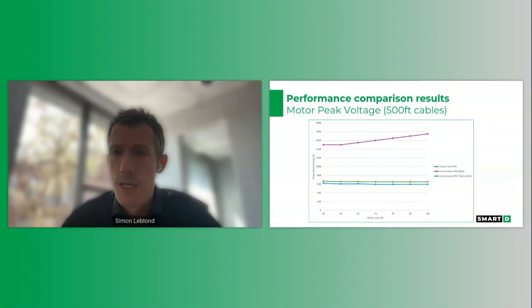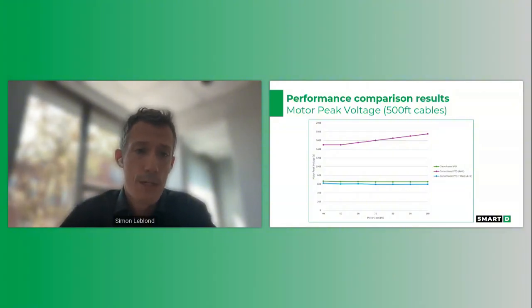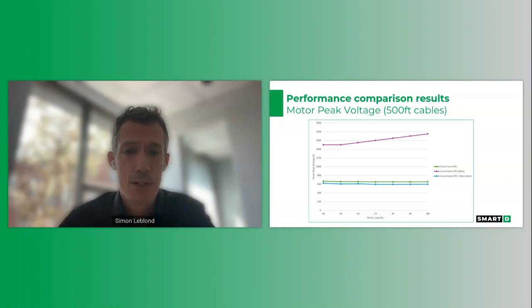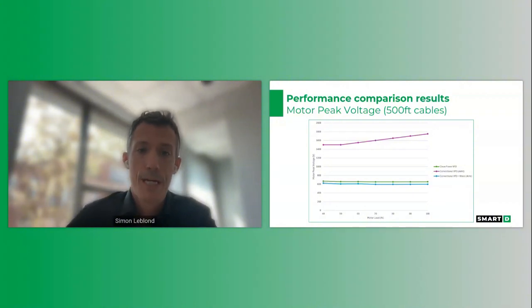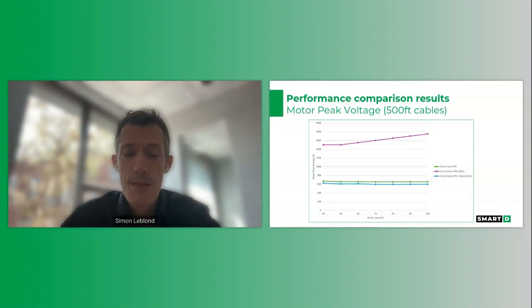Now, continuing, common mode is one of the villains you talked about, Bobby, but the other one is the motor peak voltage, which is made worse as we get longer and longer cables. In this case, with 500 feet of cable, you can see that the conventional VFD is definitely above the 1,000-volt limit that we find in many cables. Actually, we can even ask ourselves how the motor and cable can withstand this for very long when you're reaching close to 1,800 volts in peak voltage. In this case, we can see that the sine wave filter is doing its job, really maintaining a very constant peak voltage at the motor terminals. And the Clean Power VFD is doing the same, having a very flat performance. So this is what we want to see.